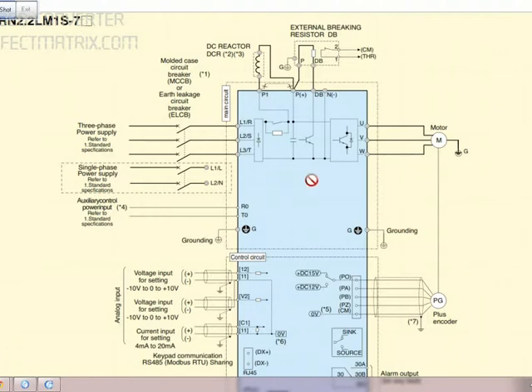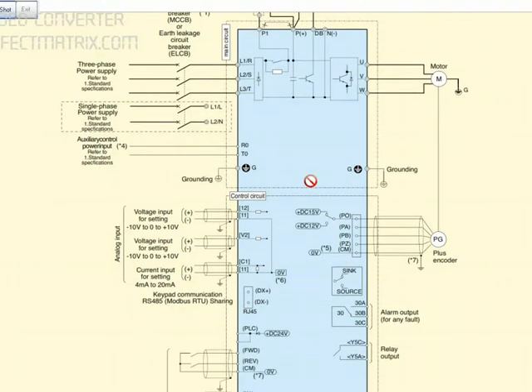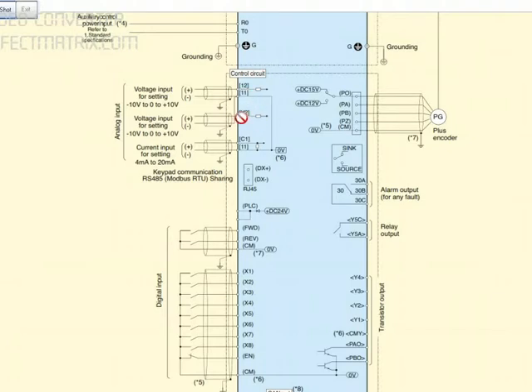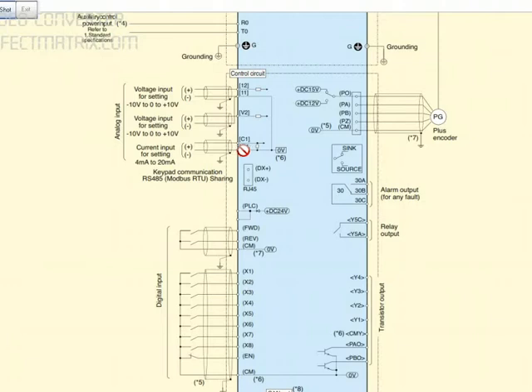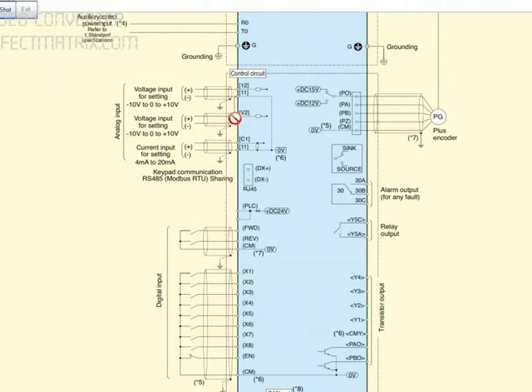So you can see the other diagrams here, how we are going to connect. We have different connections here. You can see C1, C1 is for the current input setting. And we got one more terminal 11. So these two terminals are for the current input setting. This is for 4 to 20mA. Whereas V2 is for voltage inlet voltage setting, range from minus 10 to plus 10.